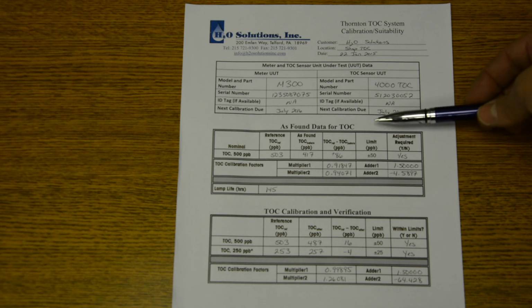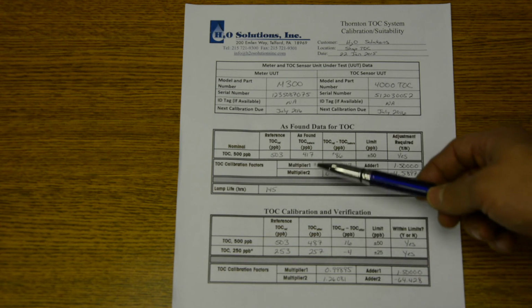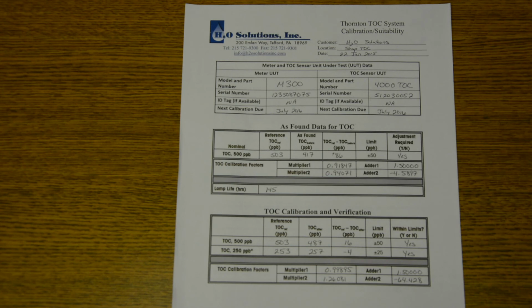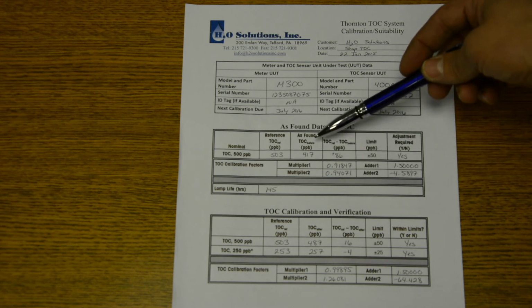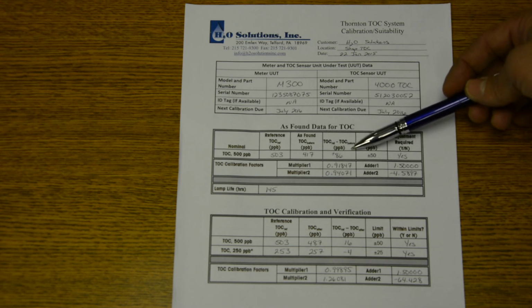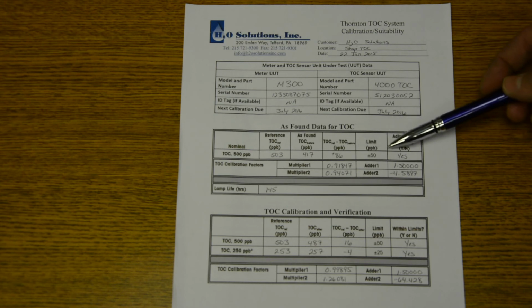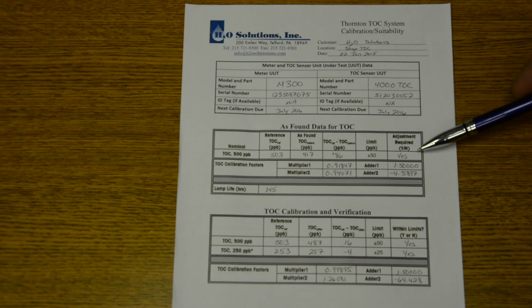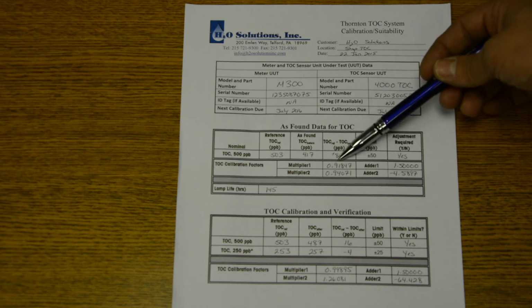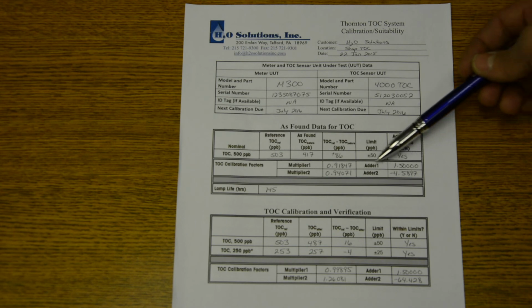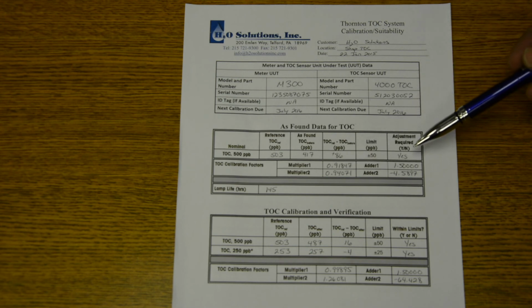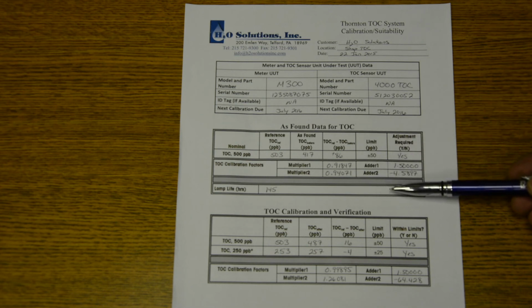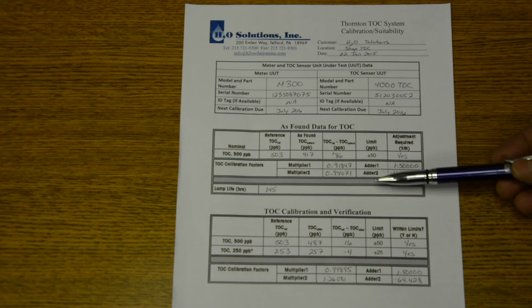Then you're writing down your as found TOC data. The first is the first test we did with the 503 part per billion, where the as found value, and the next was the subtraction of those values to find out if we were within limits, and we were not, so we did require an adjustment. So we wrote yes on there. Then this here is the multiplier and the adders before your calibration. This is the as found data before you perform a calibration, also the amount of lamp life hours that were left at the time of your calibration before you reset the timer.